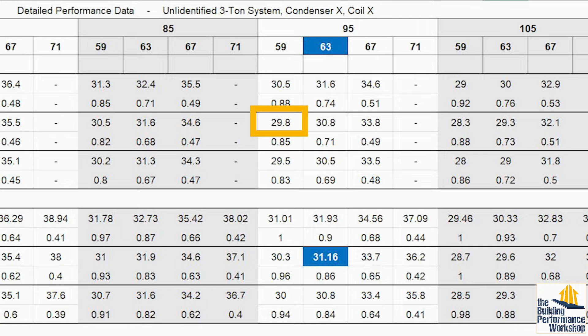And if I have a homeowner who wants, homeowners, don't set your thermostat at 70 degrees. You're setting it below the outdoor dew point. It's a terrible idea. If you're in Denver or someplace, I guess you can get away with it. It's still not very efficient, right? Remember, colder air in the return, harder to do its job, right? So the colder you make it, the harder it's going to work. If I drop this thing down to 70 degrees and a 50% relative humidity, right? That means it's going to have a 59 degree wet bulb, and that's going to be below 30,000 BTUs. By the way, that's not every 3-ton system. That's this 3-ton system, this coil, this condenser under these conditions, right? And so now my 3-ton unit has less than 30,000 BTUs.